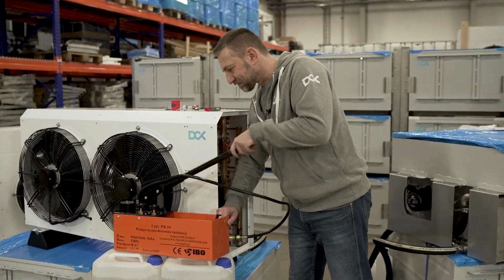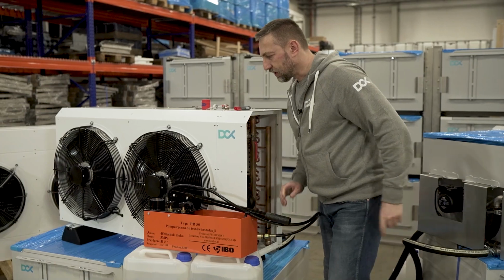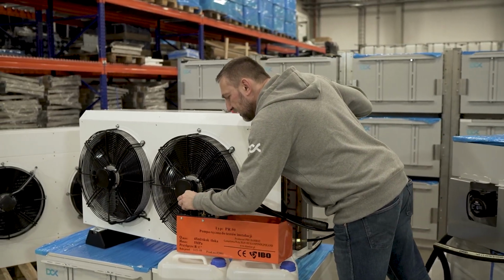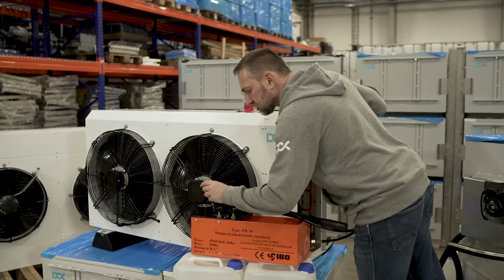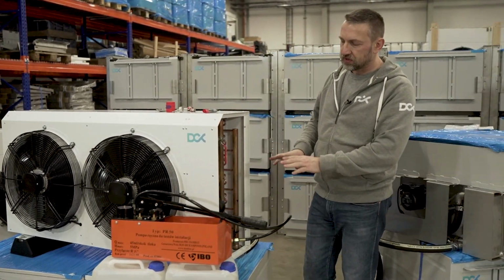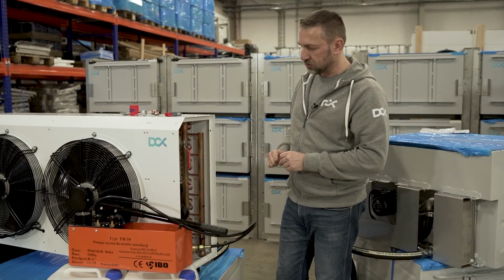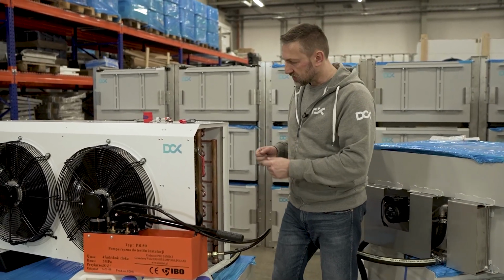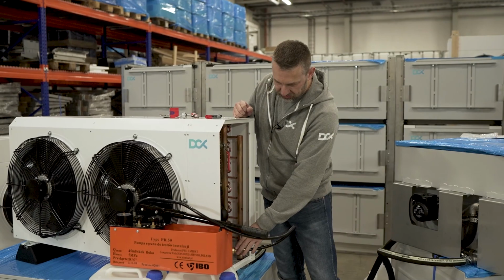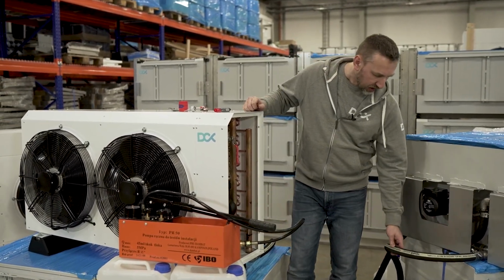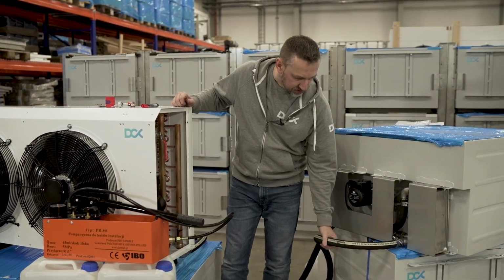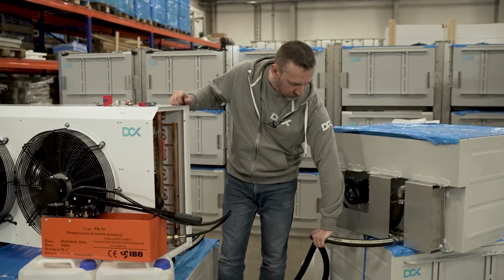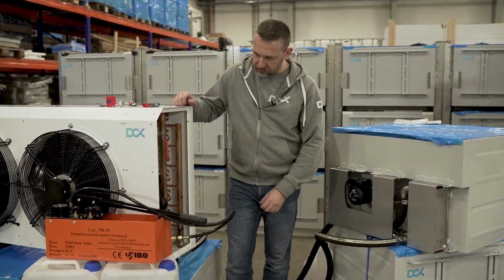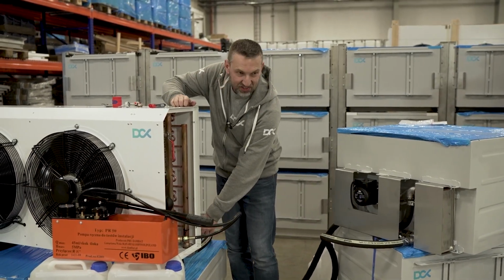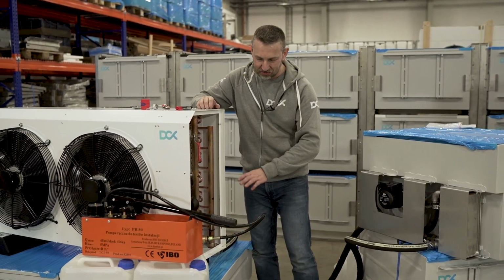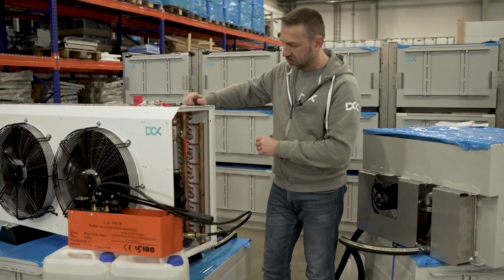Almost finished. I'm observing here that I have 6 bar, up to 6 bar, which is just indicative, and it will change in a moment when I remove the air from the system. So please observe here, I just pressurized the loop. I can feel that the hoses are pretty hard, so they're full of water. You should observe if the hoses are not having the shape of a sausage. We don't want that. That's overpressurized.